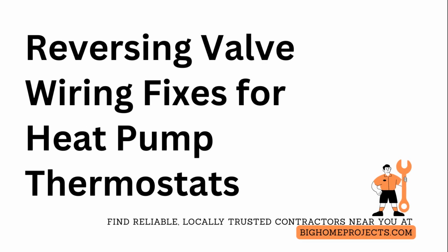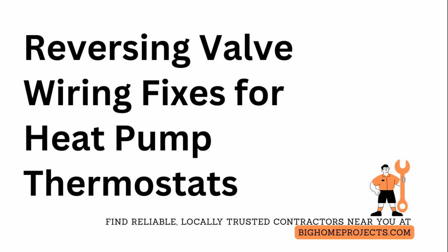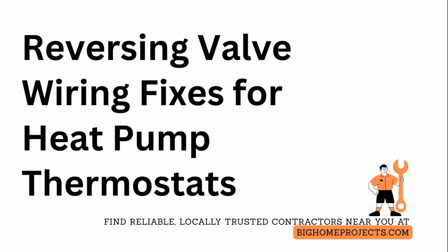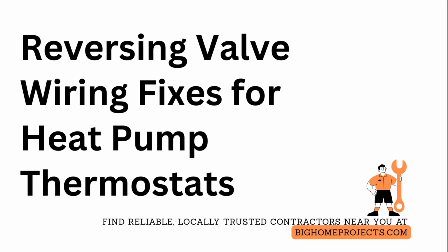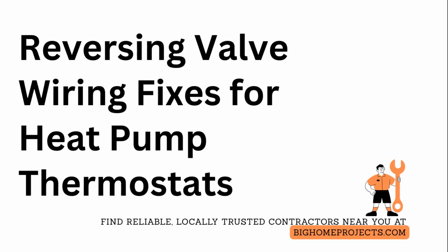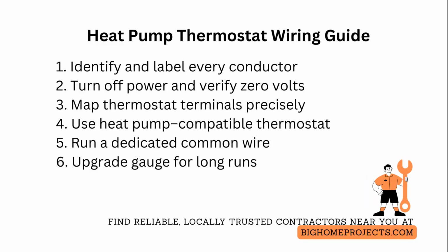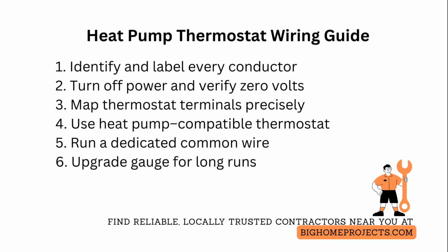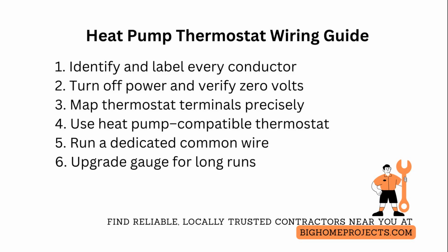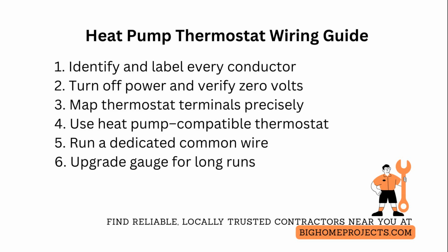Heat pump thermostat wiring needs a different approach than a standard air conditioning thermostat. Get the wiring, terminal mapping, and control logic right before you power anything up. Start by identifying every conductor at both the indoor air handler and the outdoor heat pump unit and label them. Heat pumps typically need separate wires for the four-way valve, changeover valve, auxiliary heat, and defrost control, in addition to common fan, compressor, and power, so count and verify at least 8 conductors where possible.